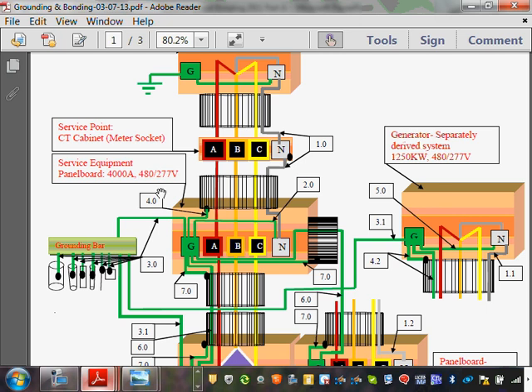Now we're at 240/120, you lost the neutral here and you're not bonded. You're running a so-called open neutral, right? What happens if you have an open neutral? The load will share the voltage based on their impedance. Some of them will take the majority of the load, some of them will take little load, and long story short, you'll burn both equipments.